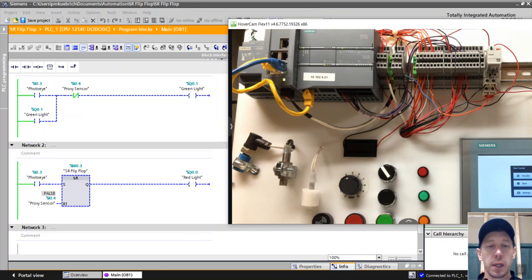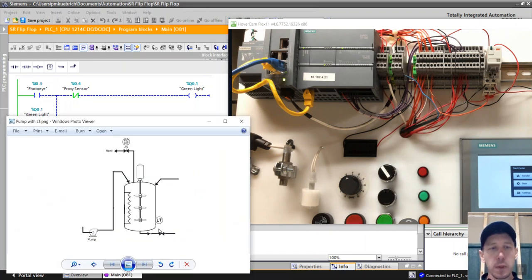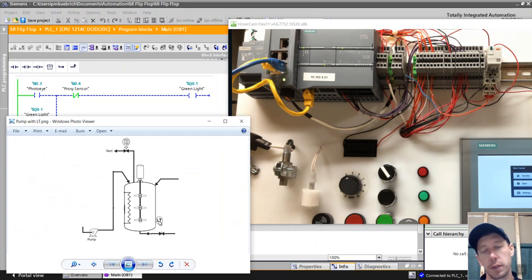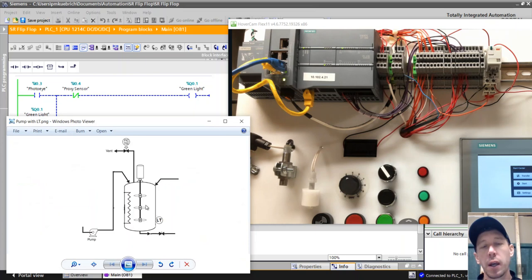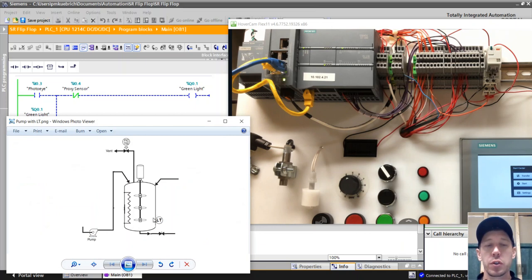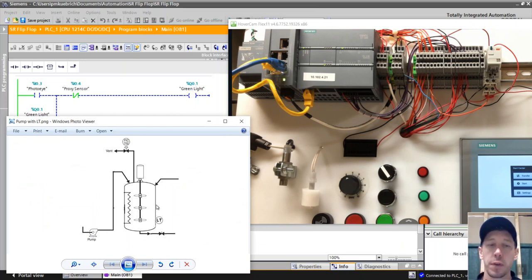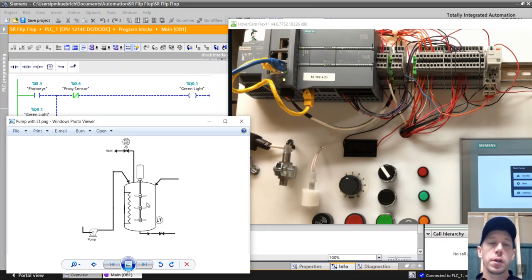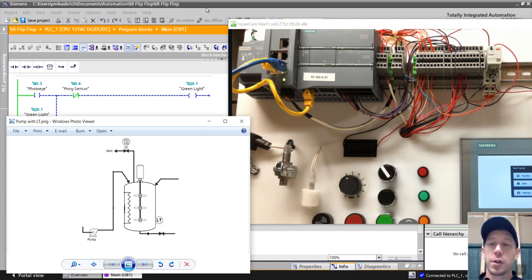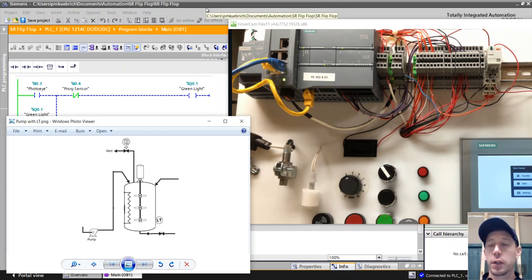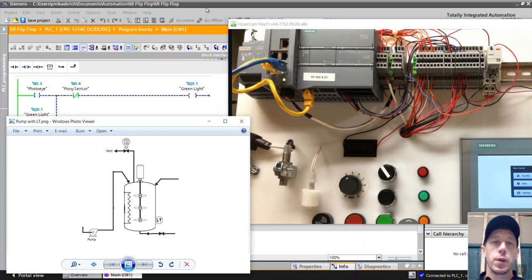What we're going to do in our case today is we have a tank with a continuous level transmitter. So this transmitter will transmit the level anywhere from zero to one hundred percent. We don't really care exactly how much water is in the tank or how much liquid is in the tank. We just want the pump to come on to refill it at twenty percent and then shut off at eighty percent so it doesn't overfill the tank. This is going to be some type of a surge tank or storage tank that we're using. As long as it stays between twenty and eighty, that's what we want. We can also use this for temperature applications. If we wanted a heater to kick on at say thirty degrees and then kick off at forty degrees, we could use this application too. This is how we can tie in to an analog circuit.